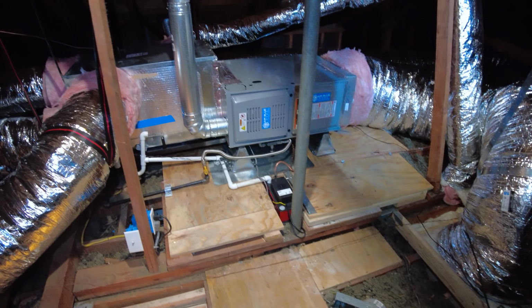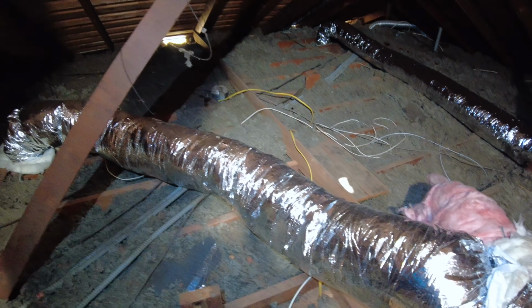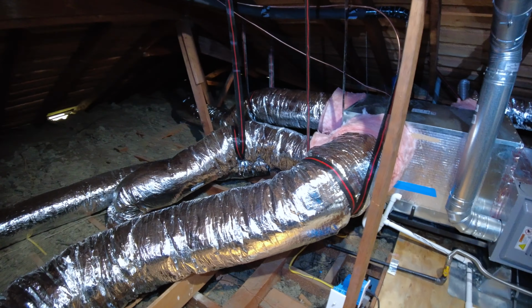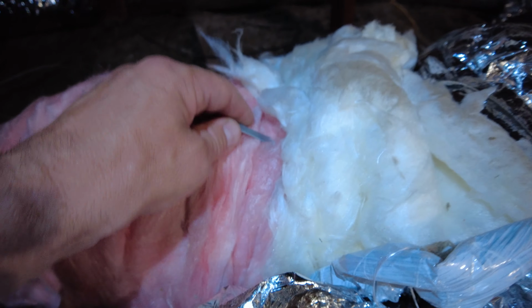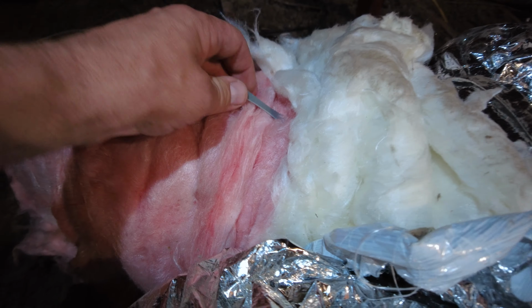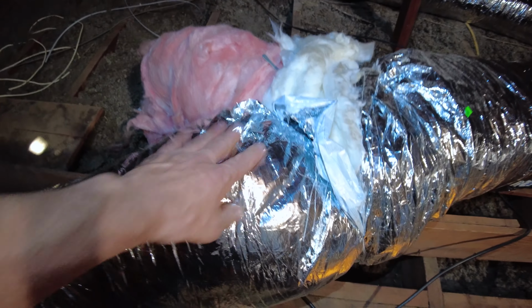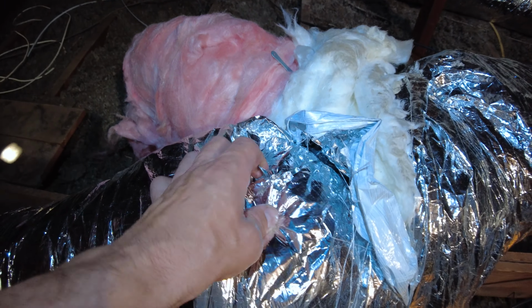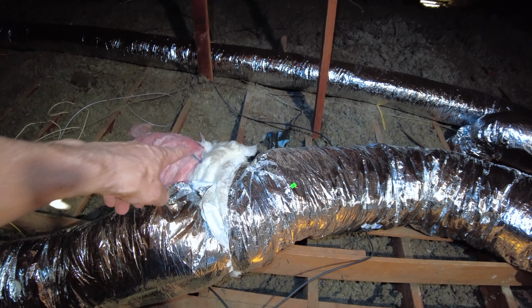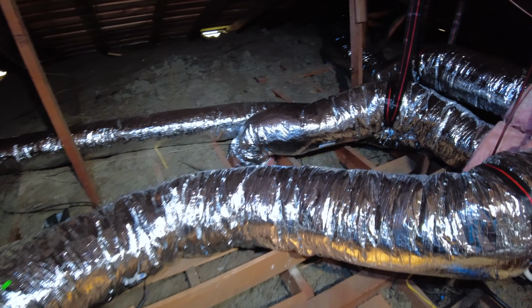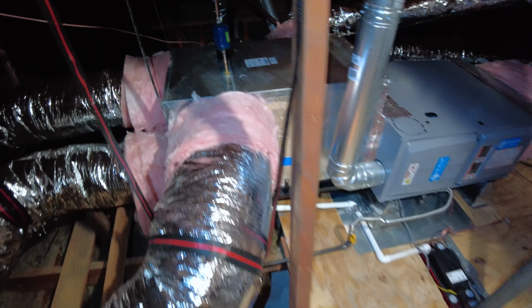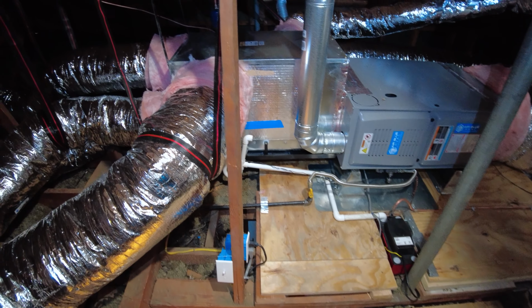Also, we replaced the ductwork. Where the duct goes into the flow box, we have metal elbows everywhere, so the ductwork will not collapse over there 20 years later. And every single duct run has a manual damper. This is a lever, so we can control airflow in every single vent in this house. That's one, that's another one. If our duct splits on a TY, we have those dampers inside the TY. If we have a duct going directly to the coil, we have those dampers right here by the coil. And usually when we do ducting, we use larger size ducting, so we never have issues with the airflow. So we almost never have to adjust those dampers in a single story house.